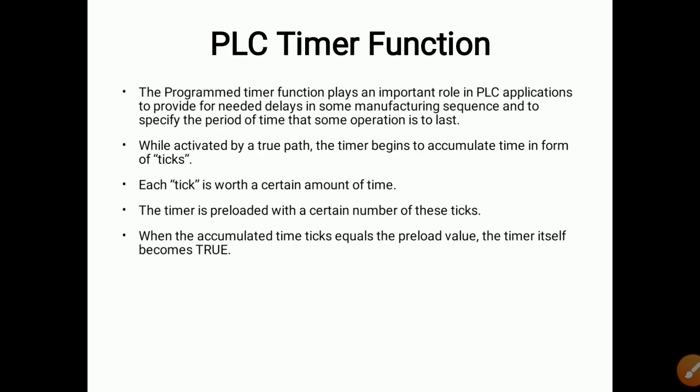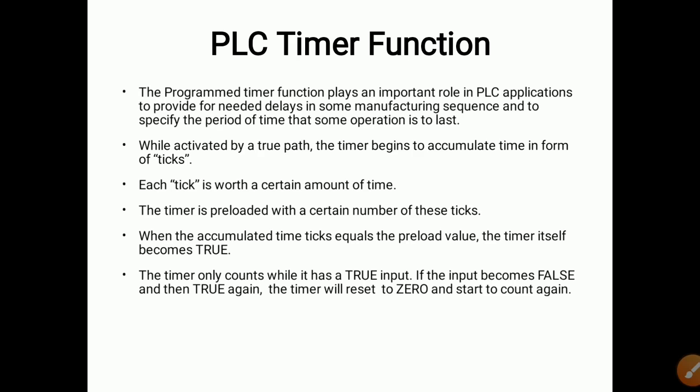When the accumulated timer ticks equals the preload value, the timer itself becomes true. We set some preload value and when the preset value equals the accumulated value, then the timer itself becomes true. The timer only counts while it has a true input.